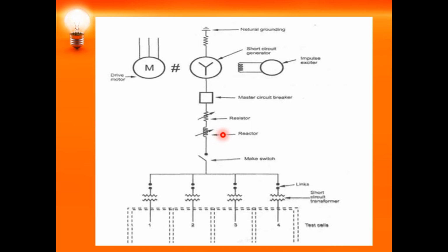Coming to this, you can even see the master circuit breaker, the make switch, and the short circuit transformer. These are the test circuit breakers, test cells 1, 2, 3, 4. And you have a motor and an impulse exciter. Now we will see each of these components one by one. First is the short circuit generator. It actually provides the power for testing.